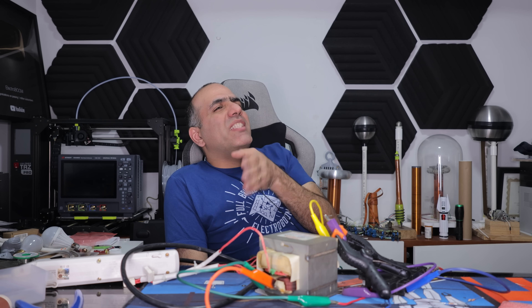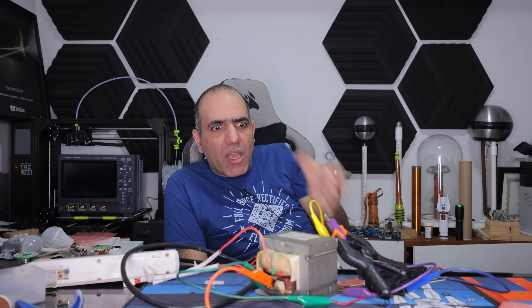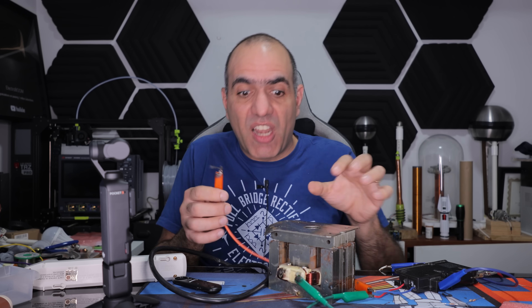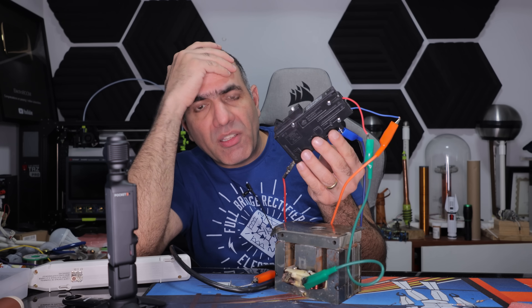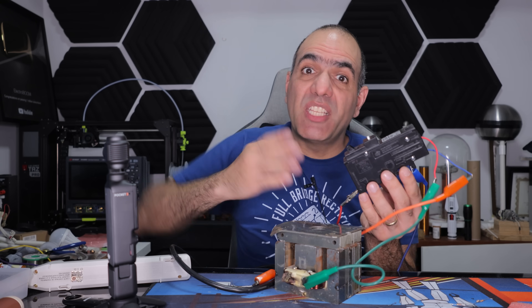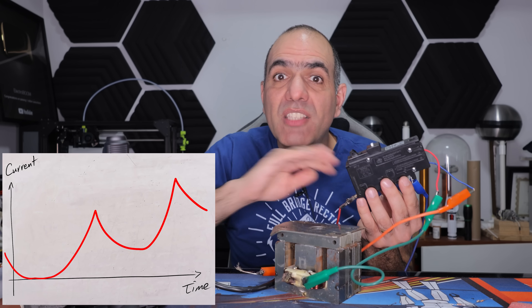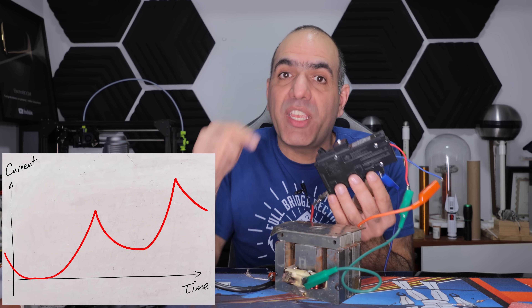Perhaps the issue was it was the output of a transformer — we need something right at the power lines. So this is just a single large inductor that draws 5 to 10 amps from the lines. Aren't these considered arcs? Why is it not entertained? I'm thinking the AFCI is looking at continuous current interruptions in the power line to detect loose contacts that might be arcing. An inductor tends to smooth out the current so it might not look interrupty enough to the breaker.